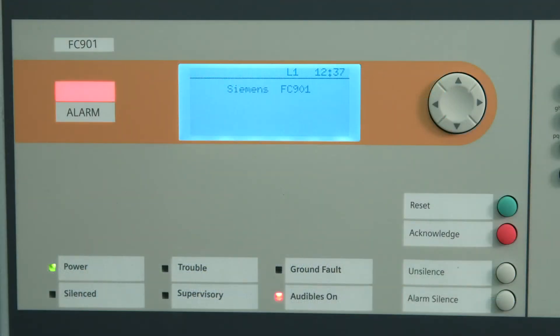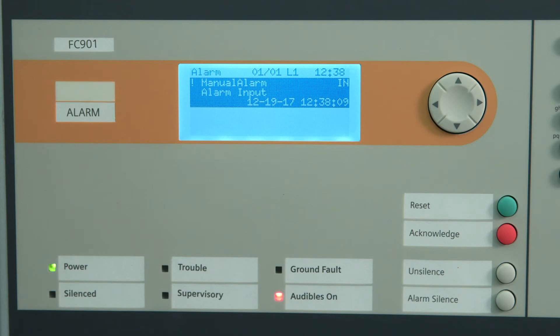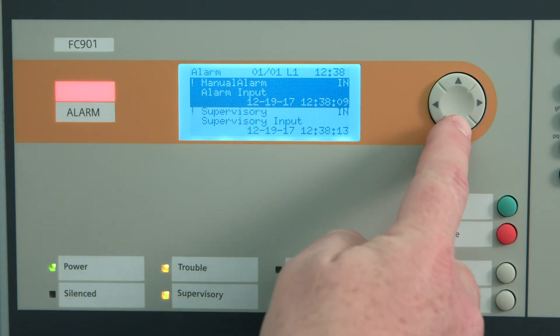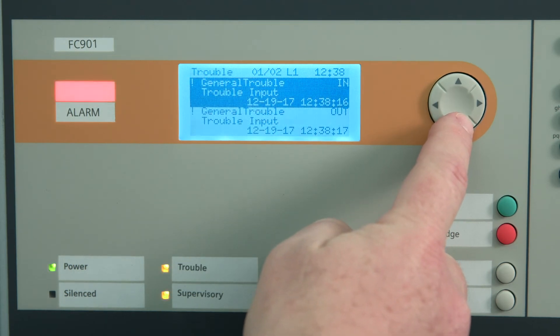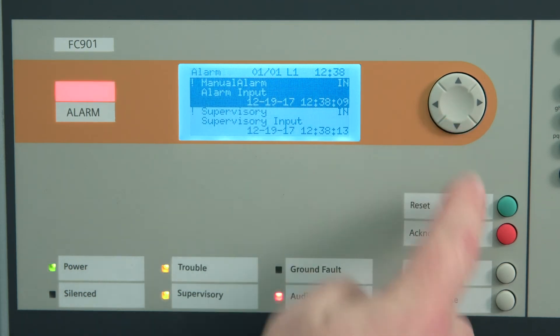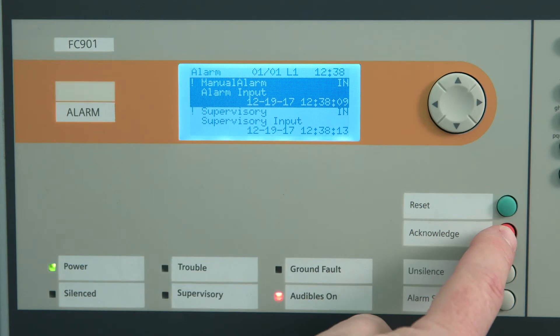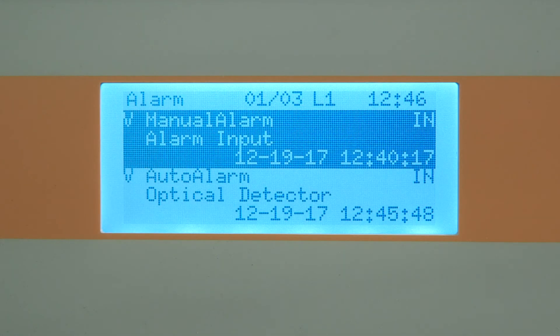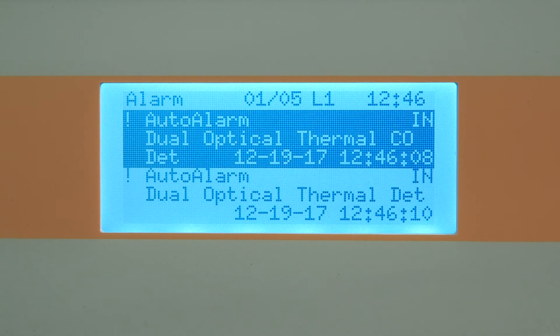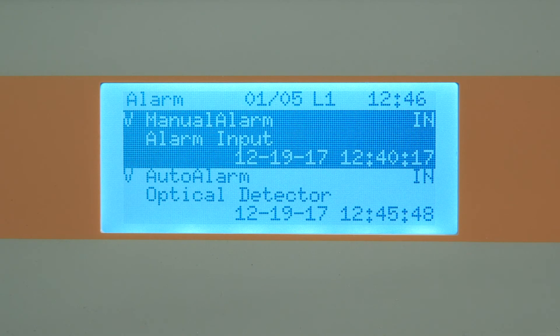Viewing events on the system: events are displayed by event priority — unacknowledged alarm, unacknowledged supervisory, unacknowledged trouble, status and test. These are followed by event occurrence from latest to oldest event in a circular list. According to your system settings, some events might not be displayed on the remote display.